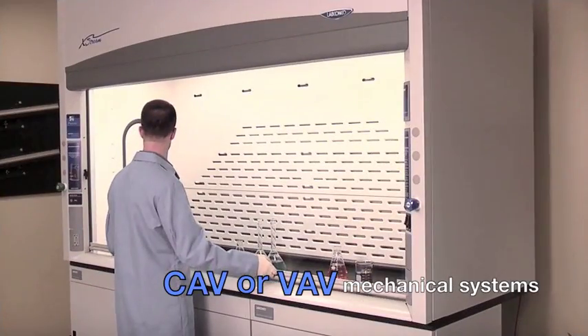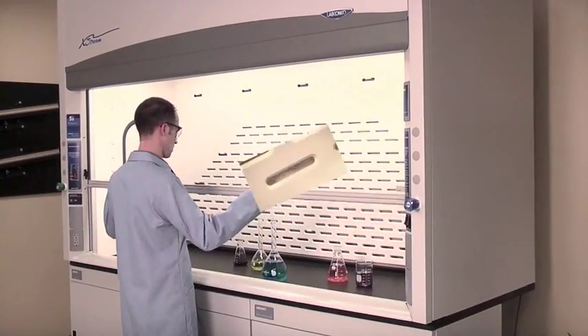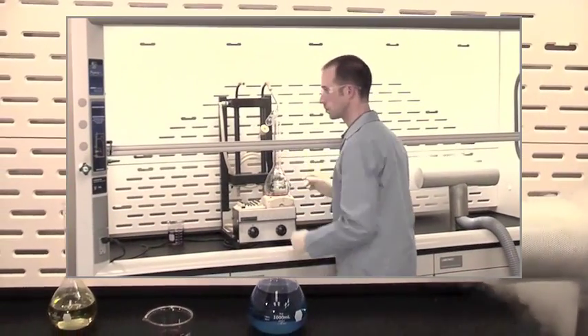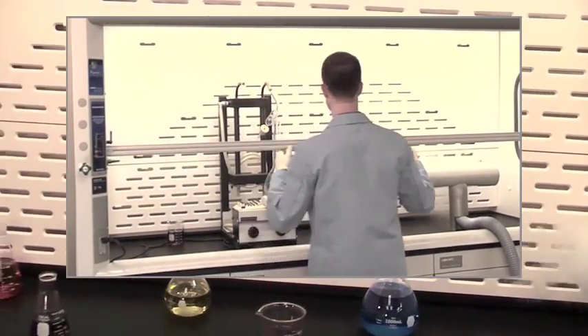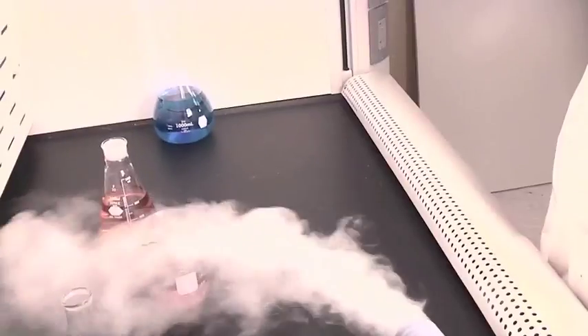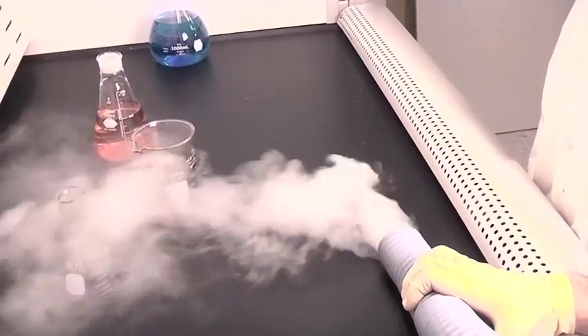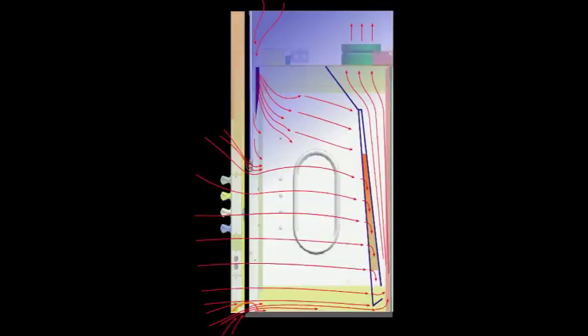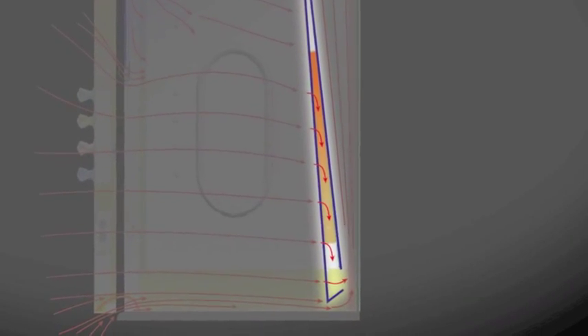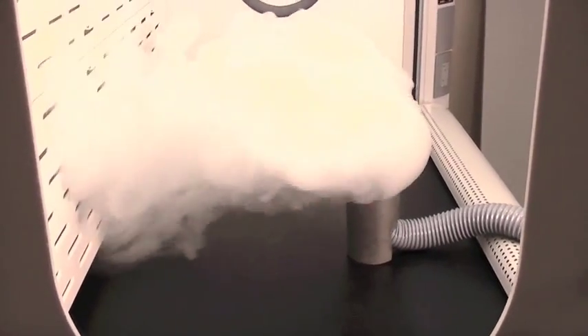The most significant and innovative feature of the Protector Extreme fume hood is the rear baffle system. When the sash is open to its energy conserving 18 inch height or optional 28 inch full open height, the slots in the primary baffle direct air in non-turbulent streams from the hood face into the baffle in a single pass. The secondary baffle, located between the primary baffle and the back wall, counteracts the upward air streams that create roll or vortex in traditional hoods.